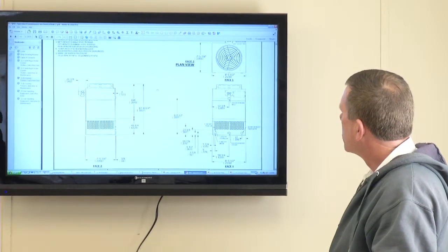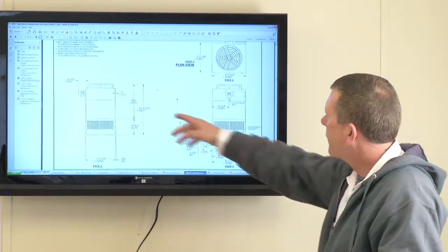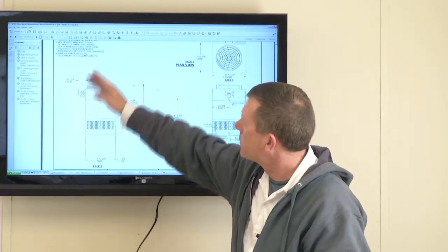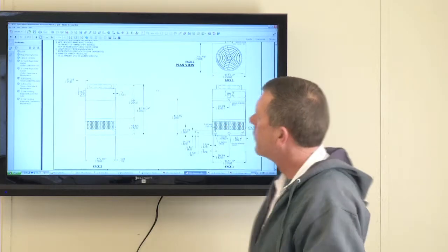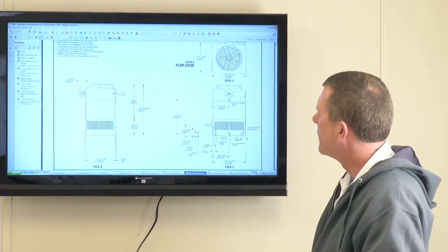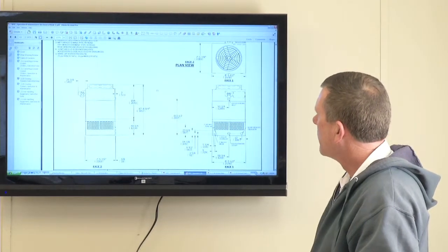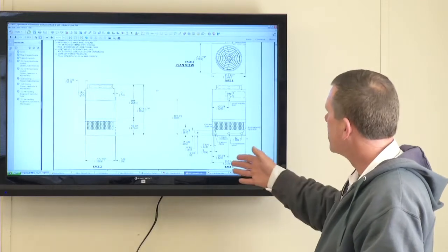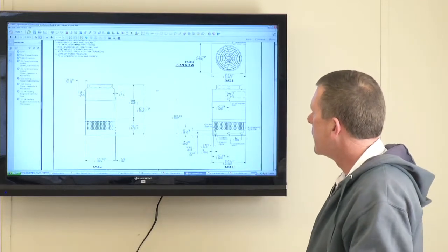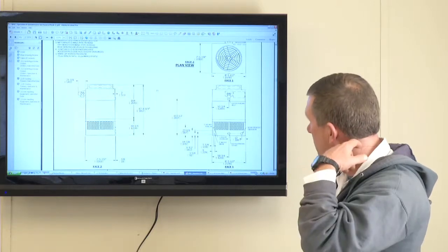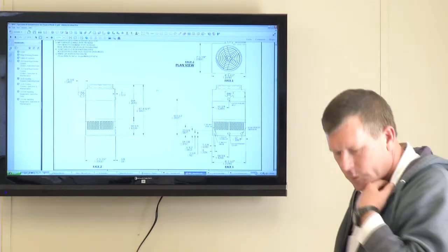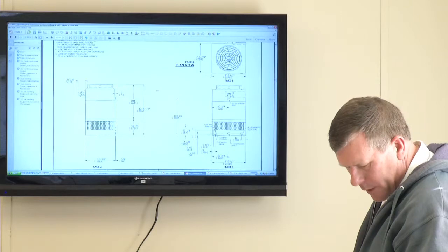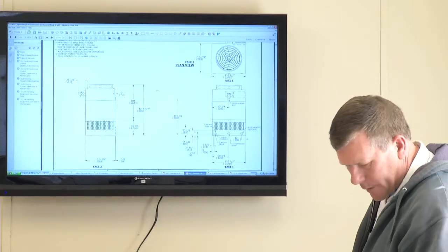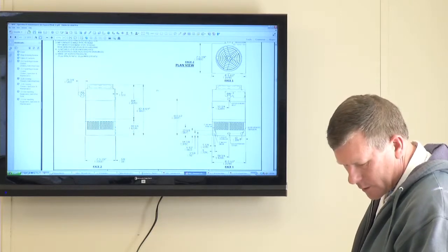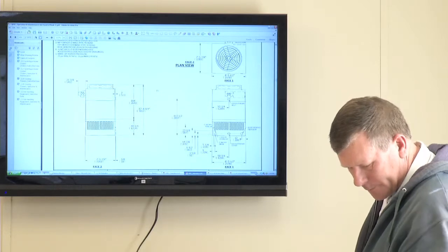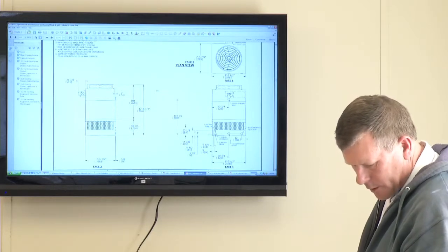As far as the motor, it sits on the outside of this tower. Here's a picture of it right here, and they also have a little jib crane on the top of it where you can put a chain fall hoist if the motor has to be removed. As far as draining, each individual tower can be shut off and the other one drained for service. As far as the operation, the bearings are to be greased every 1,000 hours, or 3 months. They're pillow block bearings.